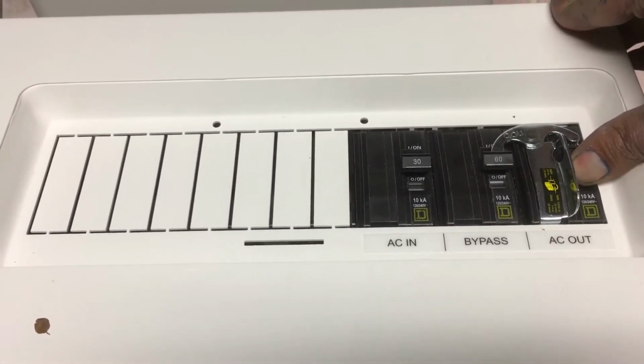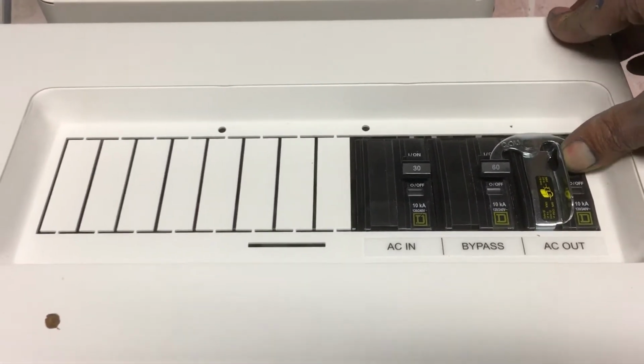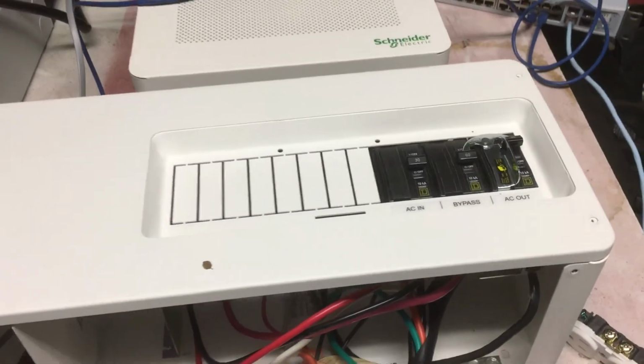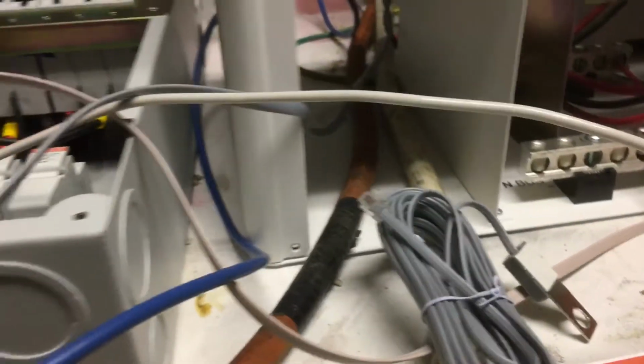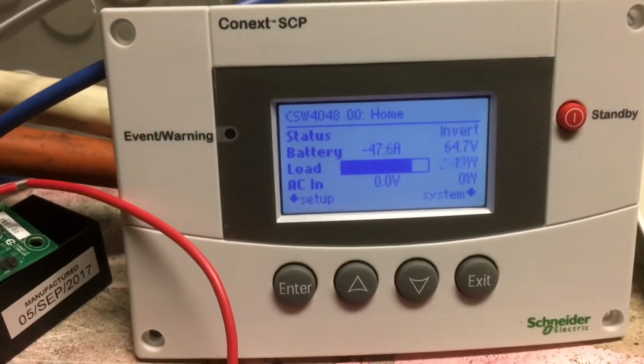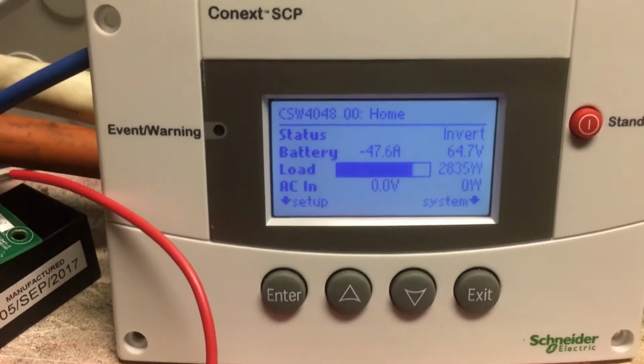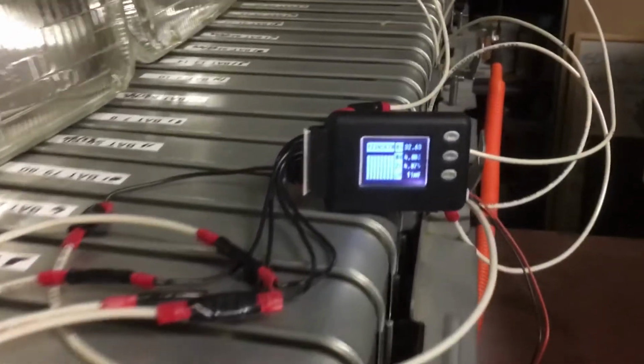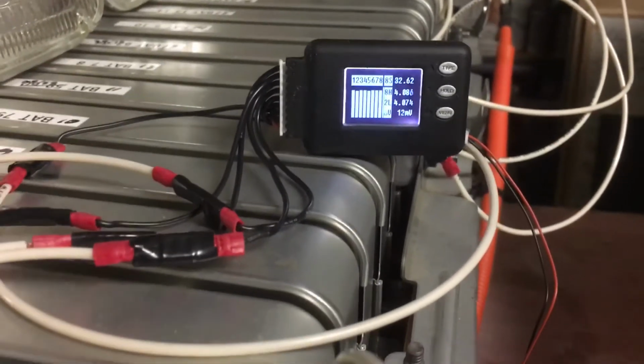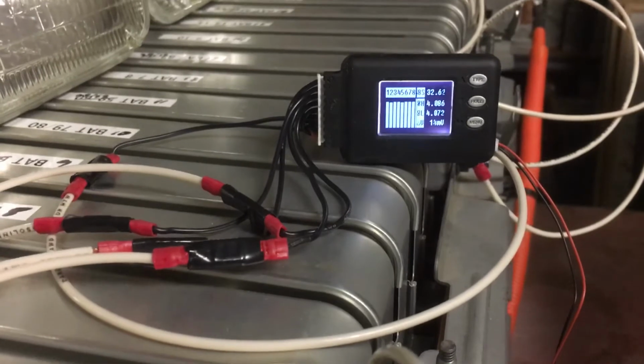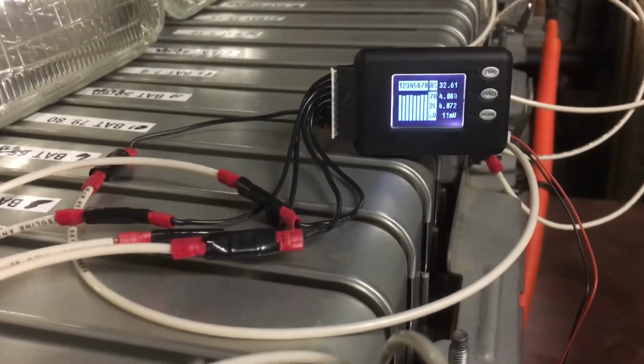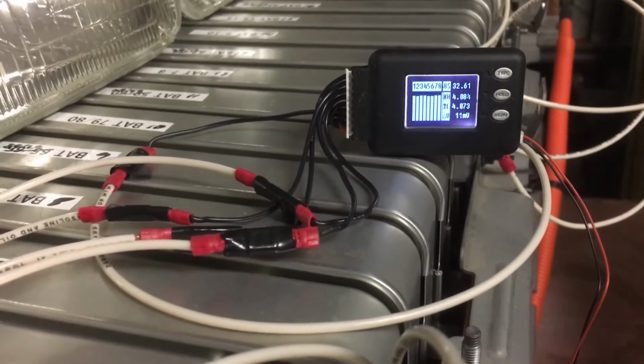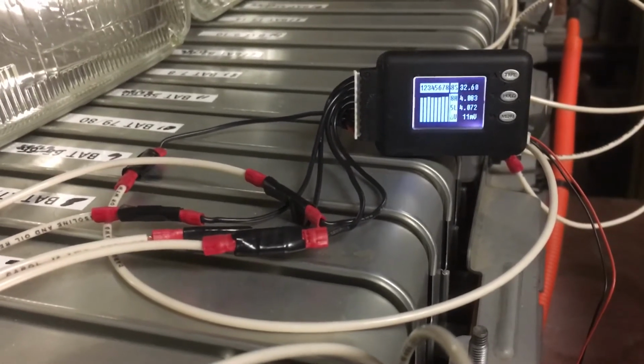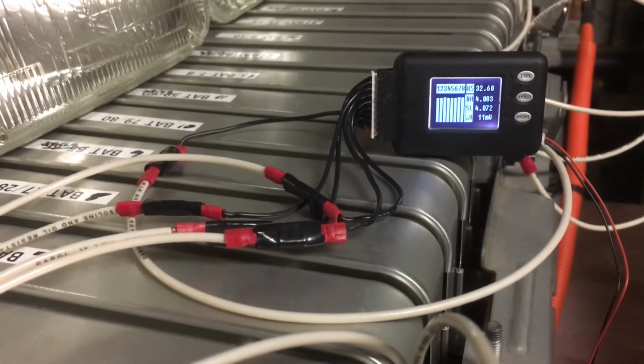I've got about 3,000 watts of load on there—just a couple of heaters plugged in. So we come over to the system control panel. We should see we've got 2,800 watts of power going out through invert mode, and we should see that voltage starting to come down. We're at 3.62. When that hits reliably 3.60 or 3.59, that contact will close, and I'll be quiet so hopefully you can hear the relay.